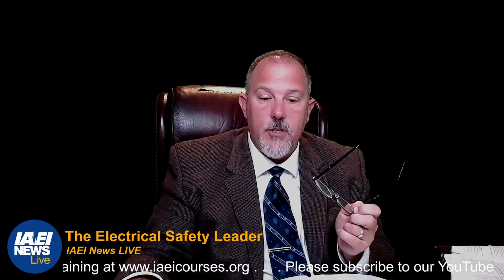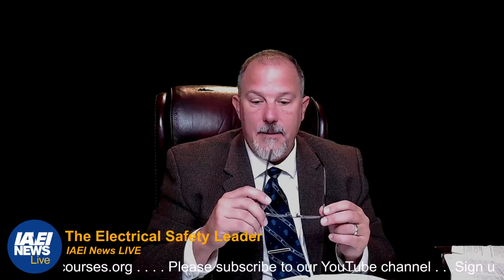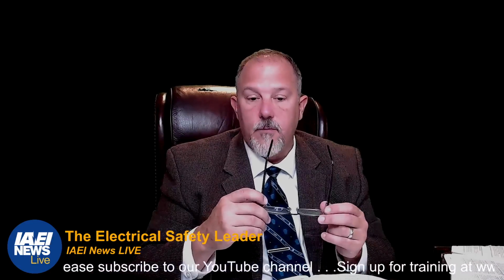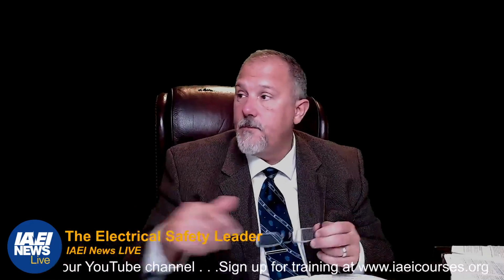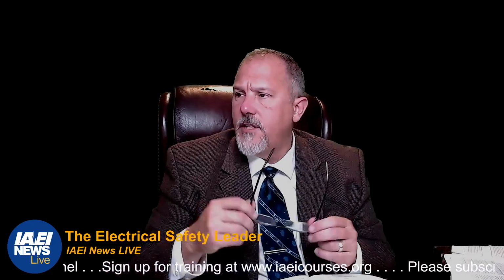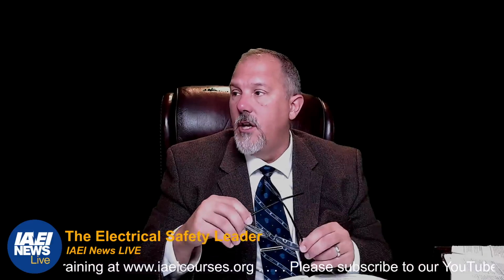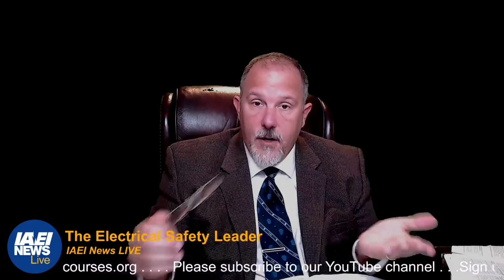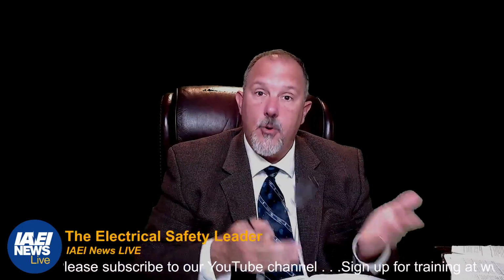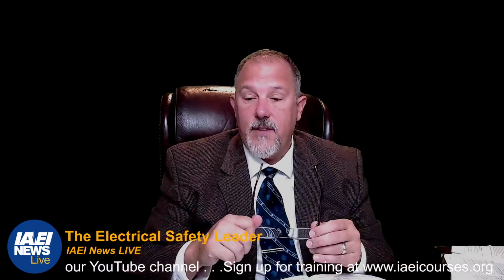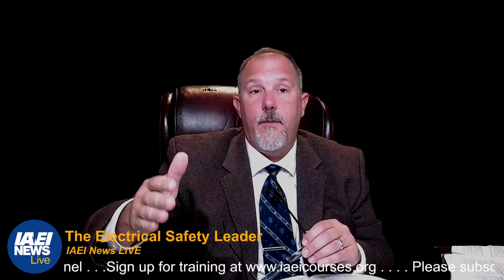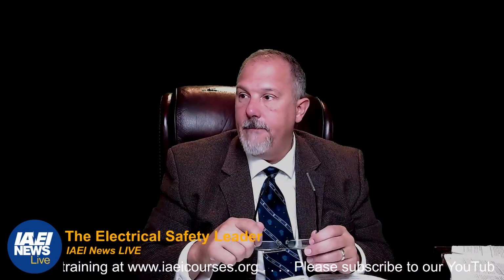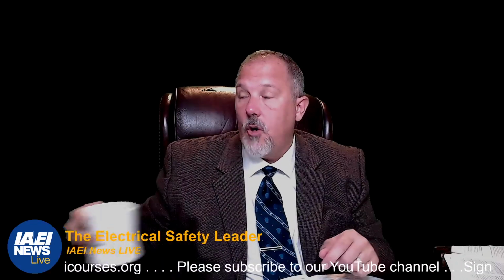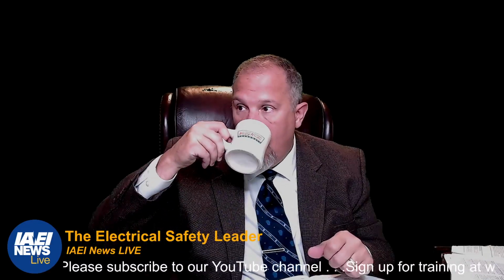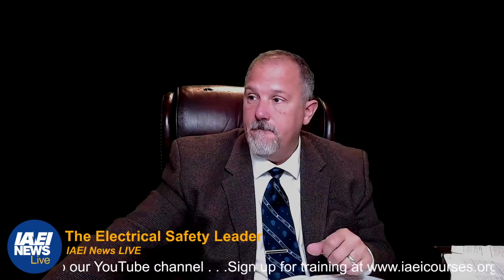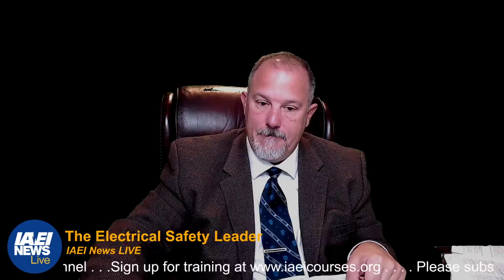We already talked about the short circuit current rating. Now, what the 2020 code did was add the field marking for available fault current other than dwelling units. So it says, other than one and two family dwelling units, the available fault current and the date the calculation was performed shall be field marked on the enclosure at the point of supply. So you've got to mark the enclosure with the available fault current. Why? Because we have to compare the short circuit current ratings, etc. And obviously you're going to have to keep those updated. But at least that tells you, ballpark, what breakers to buy. I could argue that that would change over the years, and you should maintain your short circuit labels. And that's a good 70B discussion. So that's 408.6.